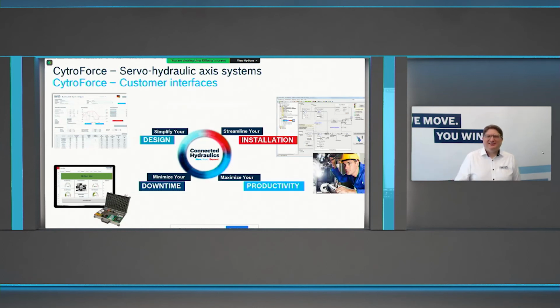On the installation side, we use Cytronics as well, and our PFC software as a position force control system, which runs on IndraWorks. There you just do your configuration, like a PID set, but a lot of parameters are already done at the plant—for example your maximum stroke and other settings, what kind of pump is inside with its limits. These parameters are already stored in a parameter file for your project and sent to you, so you just need to load this and you can start and easily set it up.